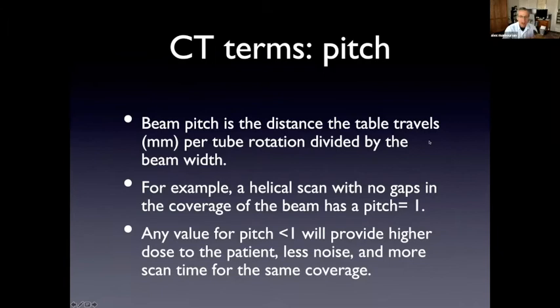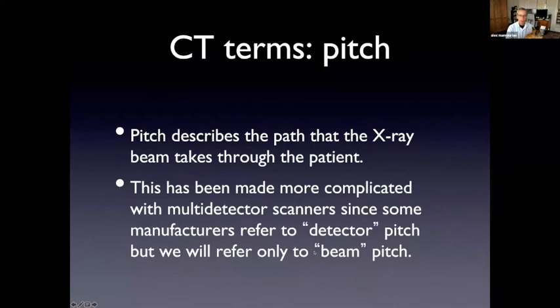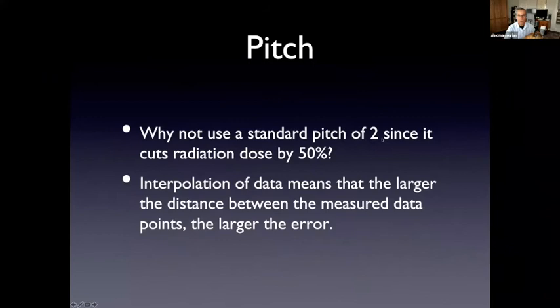So any value less than one is going to provide a higher dose to the patient, but it's going to require more scan time for the same coverage, but you'll have less noise in the image. So these are the compromises you make when you're designing the imaging protocols. If your goal is to have lowest possible scan time, then you're going to go to a higher pitch. If you want to decrease noise, you have to go to a lower pitch. So these are all compromises that you make when you decide pitch.